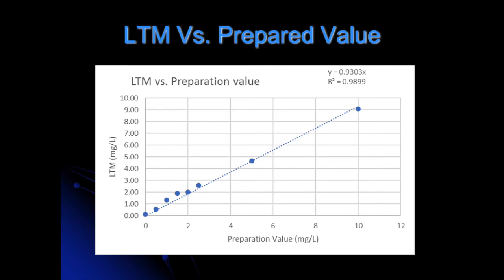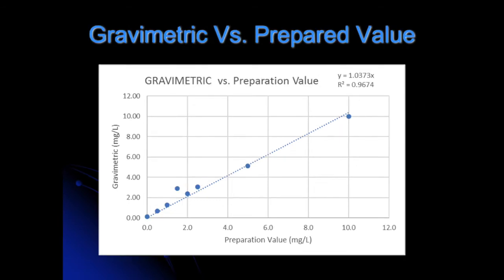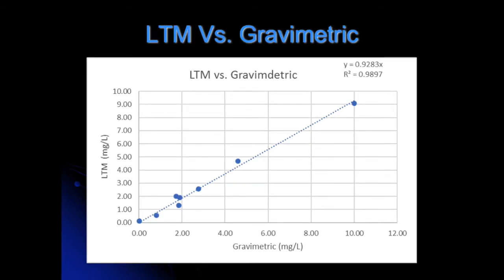As you can see from the graph, it was very accurate in determining the amount of particulate compared to the prepared value. When you compare the data from the gravimetric method to the prepared value, it determines an R-squared value of 0.9674, which is significantly lower than the R-squared value for the LTM method, and some data points are significantly further off the prepared value line. If we compare the gravimetric method, which was the industry-used method at the time, to the LTM method, we see an R-squared of 0.9897, showing that the LTM method is basically giving you the exact same information as the gravimetric method, just slightly more accurately.